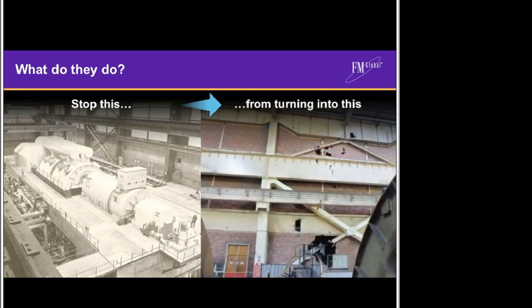However, the primary function of equipment safety devices in the context of turbines is to prevent upset conditions from causing damage to the turbine. This damage often leads to forced outages, business interruptions, and ultimately economic loss. So, appropriate safety devices that are well managed are critical to protecting turbines from upset conditions. The next question is, how do these safety devices protect turbines from that damage? Firstly, they need to detect the process upset or fault condition.